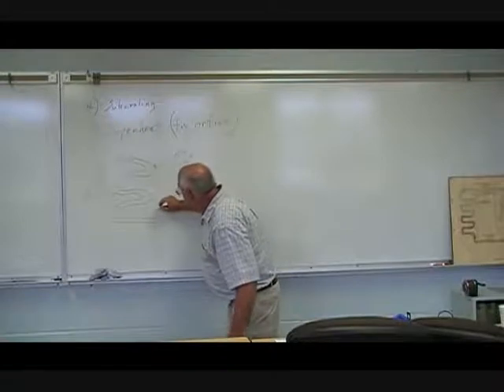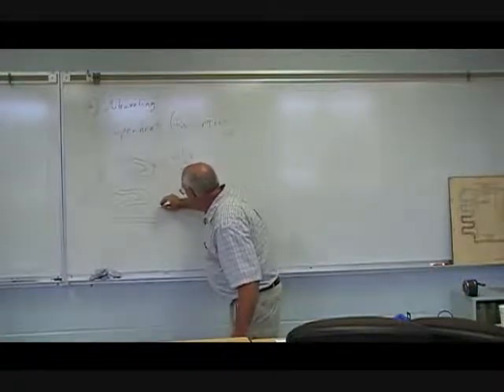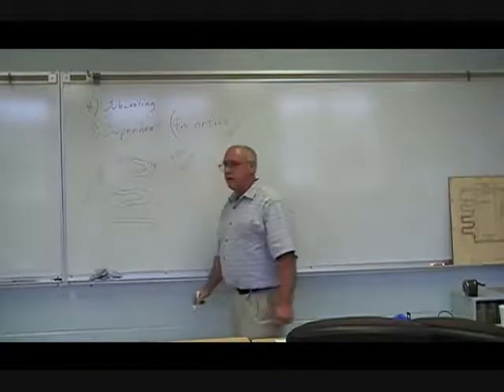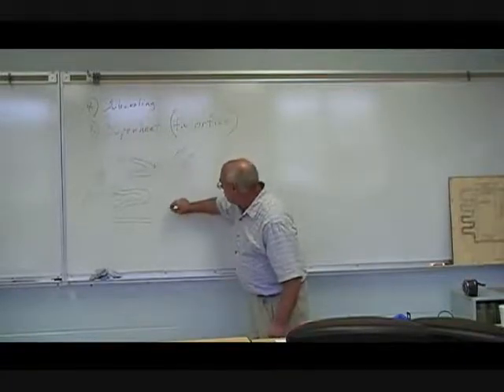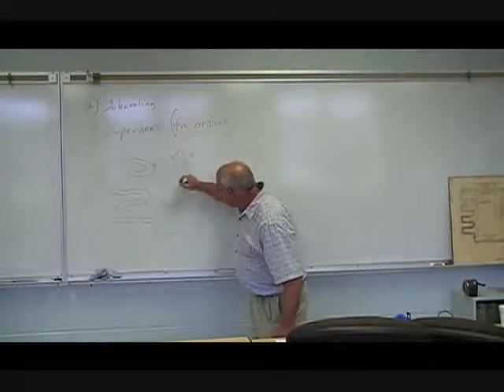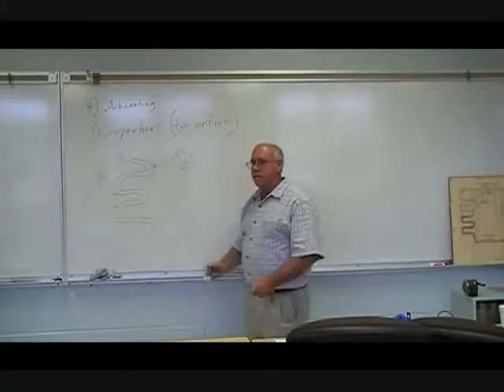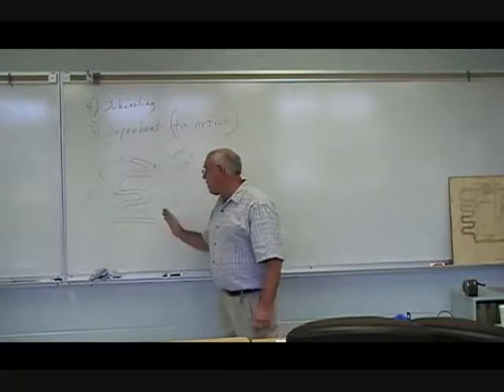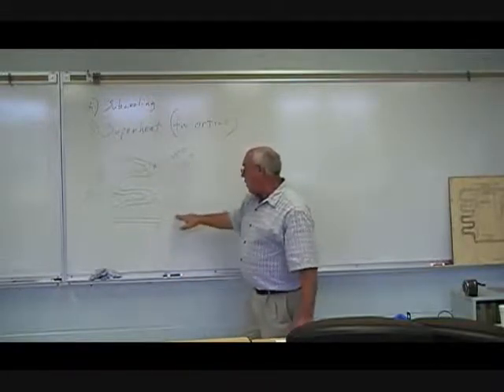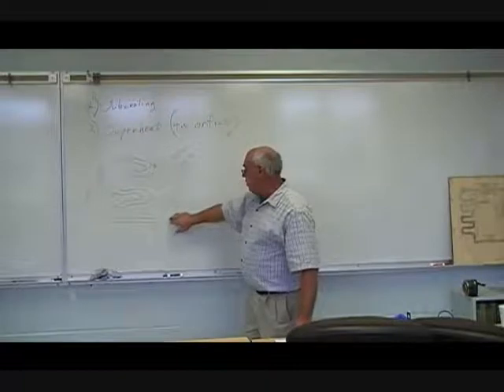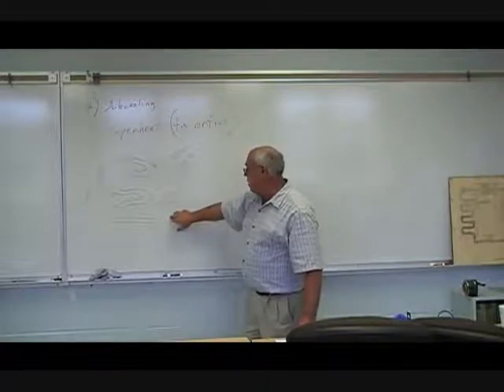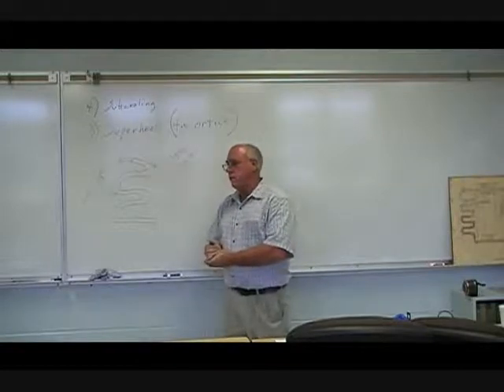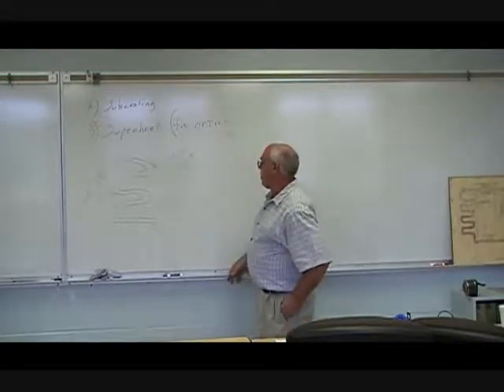Here we will probably have somewhere around 55 degrees. But what's our pressure going to be? 68. Now I'm not taking into consideration any loss across the evaporator, pressure loss across the evaporator, but the way we figure this is we're 15 to 20 degrees above the saturation point. We're guaranteed that we're not going to have any liquid coming back to the compressor.